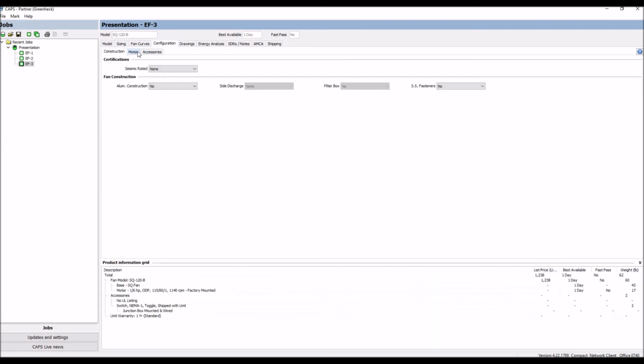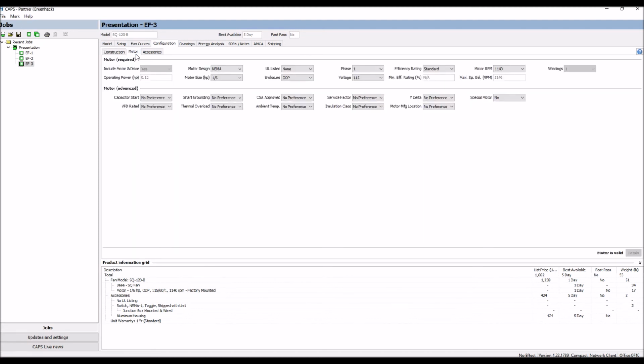For example, maybe we're putting this on a VFD. The VFD is out of the space, so it won't need to be in a NEMA 7 or 9 enclosure. And I'll select aluminum construction. So that's basically saying, I've got an aluminum fan wheel, now it's in an aluminum construction, so I'm only stepping up what I'm meeting the intent, the spark resistant. So arguably you could be closer to B or A versus being closer to spark C. But again, we're meeting the intent.